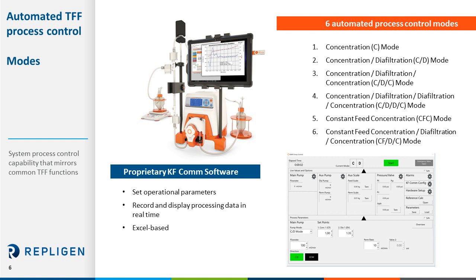The KR2i pump can be controlled manually or automatically with six different automated TFF modes. The modes of operation include concentration, diafiltration, constant feed concentration, and combinations of these. Users can input the desired operating TFF parameters through the KF Comm interface. KFCOM will also record and display process data including pressure profiles, concentration factors, and filter flux in real-time. The control screen is easy to navigate and displays pump rates, weights, and pump modes. Both operational and data collection screens are Excel-based so that data can be easily accessed on other computers.